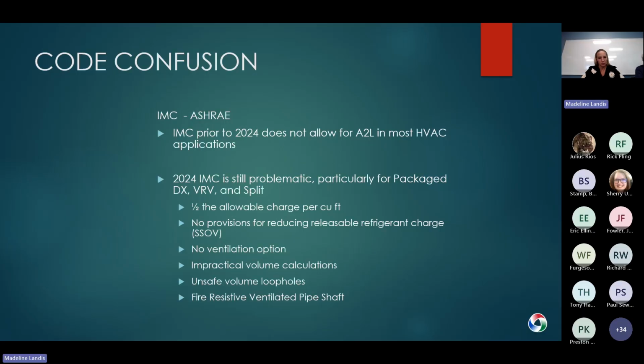However, the jurisdictions are officially on the IMC, right? Even the 2024 IMC is kind of problematic, particularly for package DX and VRV splits. It starts off with only half the allowable charge per cubic foot. It's based on 25% of the LFL rather than 50% of the LFL for listed equipment.